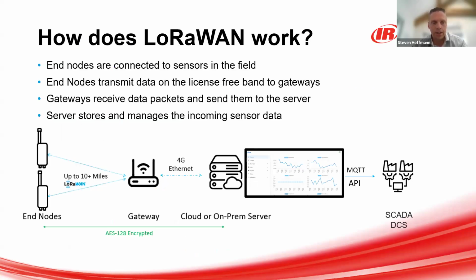So how does LoRaWAN work at a high level? You've got the end nodes, which would be those hazardous area devices you're seeing in the previous picture that are connected up to the sensors in your process, sending that data up to 10 miles to a gateway. That gateway forwards that data on to a cloud server. And ultimately from that cloud server, you can bring that data out to other applications if you want to, through MQTT or other APIs that we can integrate in there, so that you can view that data wherever you want to see all your data together. Next slide, please.